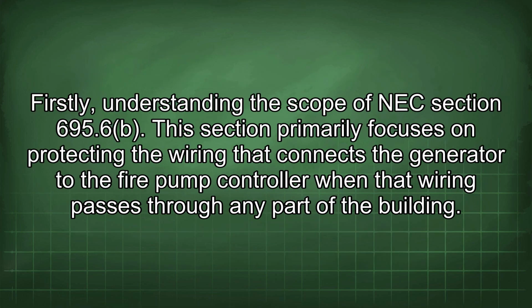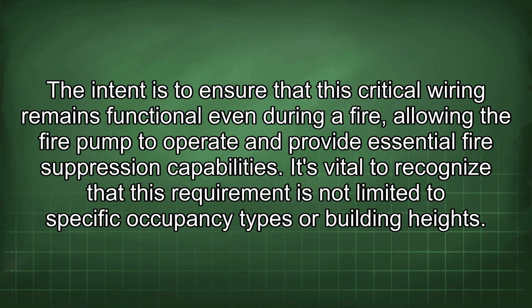Firstly, understanding the scope of NEC section 695.6. This section primarily focuses on protecting the wiring that connects the generator to the fire pump controller when that wiring passes through any part of the building. The intent is to ensure that this critical wiring remains functional even during a fire, allowing the fire pump to operate and provide essential fire suppression capabilities.